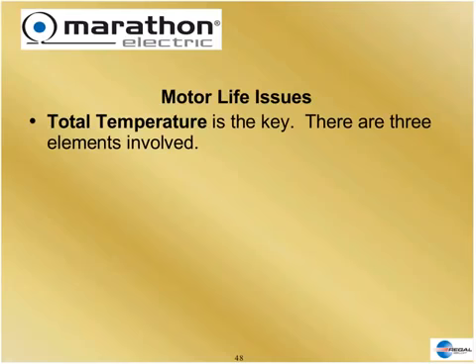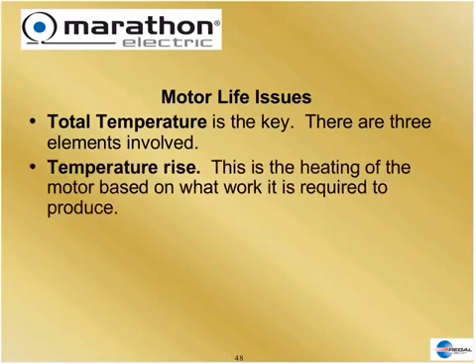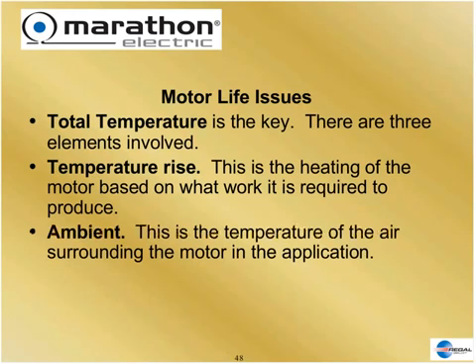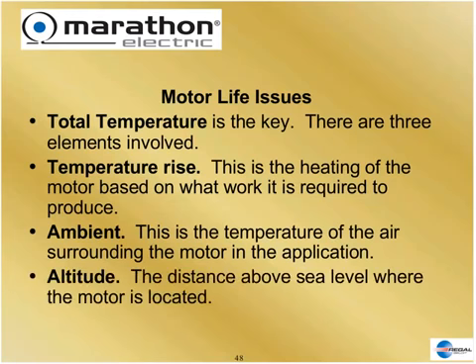The total temperature the insulation system cares about has three elements. First is temperature rise — the heat the motor produces to do its job. Second is ambient temperature — the surrounding air or medium that surrounds the motor in the application; this is part of the application, not the motor design. Third is altitude — at 10,000 feet, the air is thin with fewer molecules, so it won't transfer heat as well and the motor will run hotter. The higher you go in altitude, the hotter the motor will get.